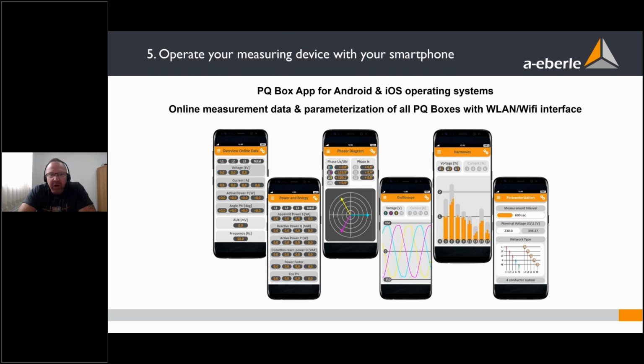We have a nice app for Android operating systems and also for Apple operating systems. You see all the online data, often with a high resolution on your smartphone. You see the online oscilloscope waveform. You see the bar graph of all harmonics with the limits also included in the same picture. The phasor diagram, the load, the power, the energy, a lot of data you can analyze directly with your smartphone coming from the analyzer. And the second feature is you can do all the settings of a PQBox. It's not a must that you connect your PC, your software, to the device. You can easily do all the settings with your smartphone.